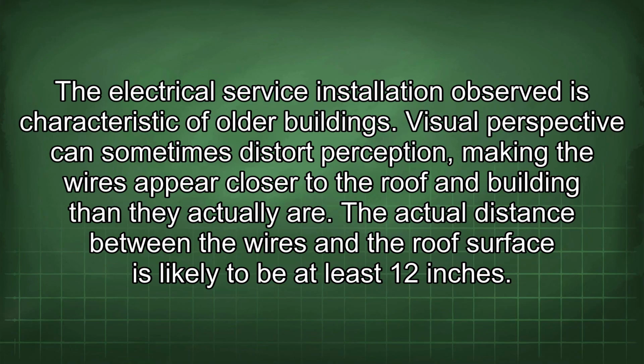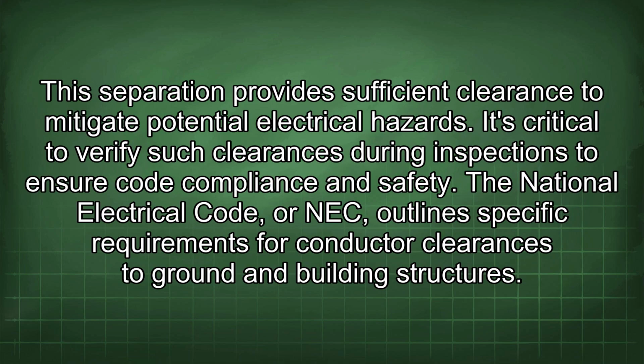The electrical service installation observed is characteristic of older buildings. Visual perspective can sometimes distort perception, making the wires appear closer to the roof and building than they actually are. The actual distance between the wires and the roof surface is likely to be at least 12 inches. This separation provides sufficient clearance to mitigate potential electrical hazards.